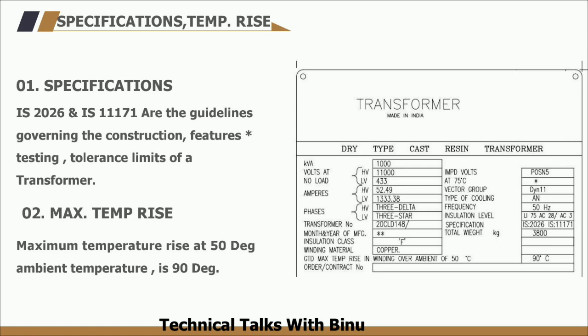Next are the specifications, showing compliance of the transformer with IS2026 and IS11171. These are the guidelines governing the constructional features, testing, and tolerance limits of the transformer. It can also be seen that the maximum rise in winding temperature will be 90°C at an ambient temperature of 50°C.